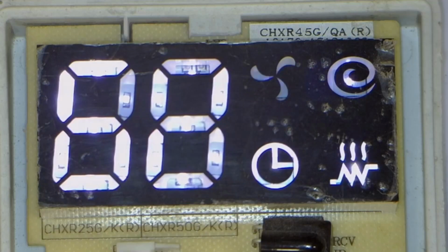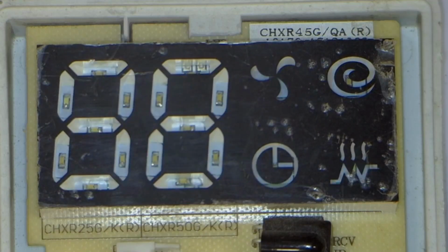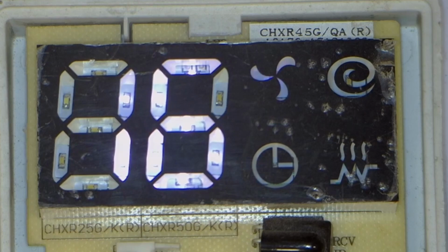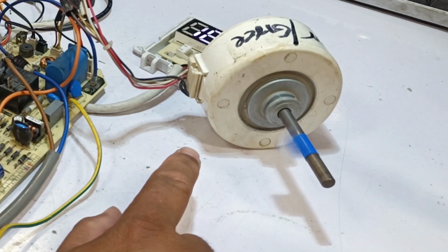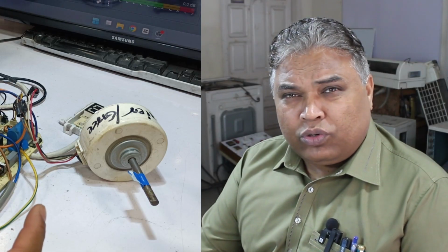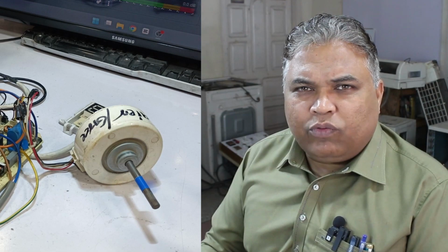However, I will explain it to you step by step, because if I tell you directly, you won't understand how to actually find it. I have now turned on the electricity, and look, the display turned on once and then turned off. And now, look, it has turned back on, and it has also started the indoor fan motor. Whenever you encounter such a fault, you must physically inspect which components are causing the problem. This will make it easier to detect the fault. Now, the fan motor started once and then stopped. Now it has started again.